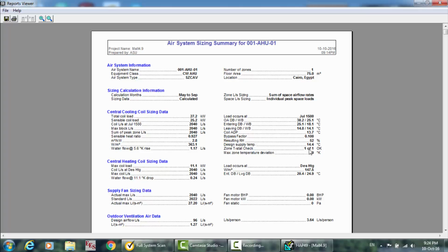So if you notice that this is red, and here is 0 of 1 or 0 of 2 or 1 of 2 or 1 of 3, this means that you have a zone where the temperature will be more than 25, more than the throttling range, and you will find the deviation here. Here it is 0 Kelvin, so there is no problem. But if there is a deviation from the throttling range, it will be written here. Suppose that we have a problem, and this is in red, and HAP tells you 0 of 1 for the zone throttling range, and the maximum zone temperature deviation is 0.8.